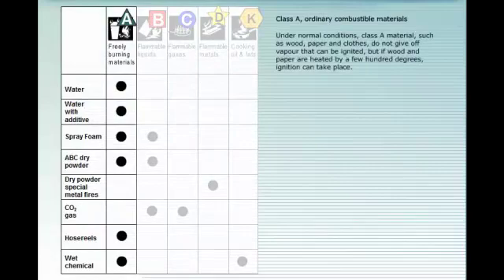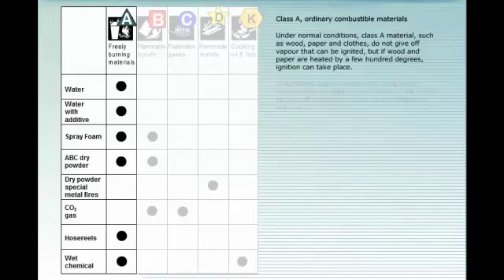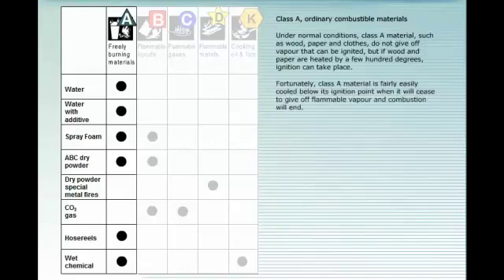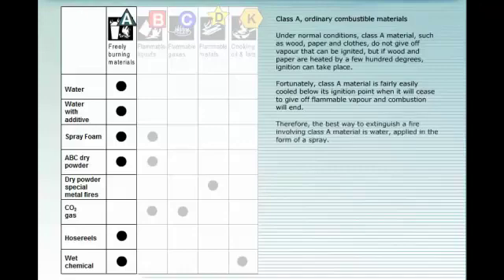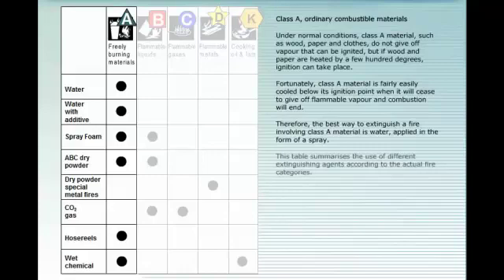Under normal conditions, Class A material such as wood, paper, and clothes do not give off vapour that can be ignited. But if wood and paper are heated by a few hundred degrees, ignition can take place. Fortunately, Class A material is fairly easily cooled below its ignition point, when it will cease to give off flammable vapour and combustion will end. Therefore, the best way to extinguish a fire involving Class A material is water, applied in the form of a spray. This table summarises the use of different extinguishing agents according to the actual fire categories.